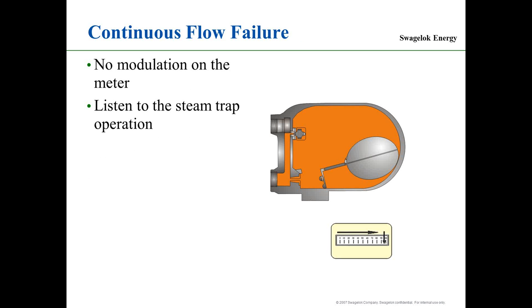So, no modulations. It's up there, as I show here on the meter, full scale, no modulation. If you're listening to it, like I told you, you need to listen to it. You hear a high-pitched whistling sound. So, two traps, on-off, continuous flow. Don't get any easier than that.